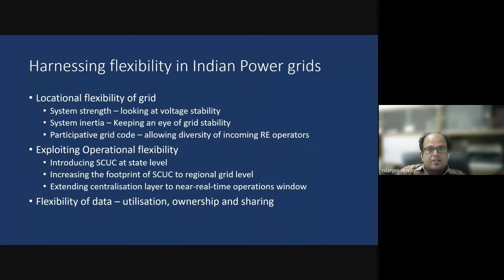So two key challenges remain in our country. Number one, unexpected fluctuations in generation can reduce grid security and reliability, and impact the operating pattern of existing conventional synchronous generation. Then significant reactive power footprint, and this may lead to voltage instability and, of course, unacceptable power factor operations. So we need to come up with a solution which must be technological, commercial, and regulatory in nature, so that our zero cost renewable energy is not curtailed in order to make way for non-zero cost conventional generation. And that is what is happening today. Our renewable energy is being curtailed.